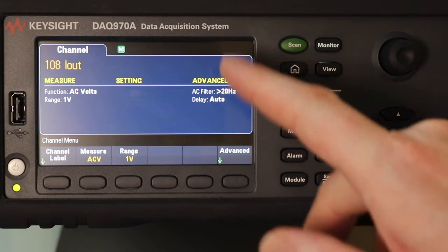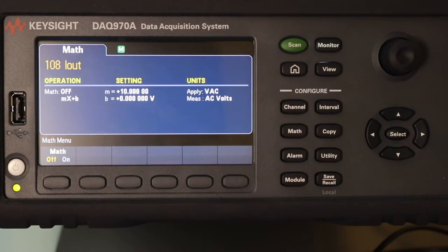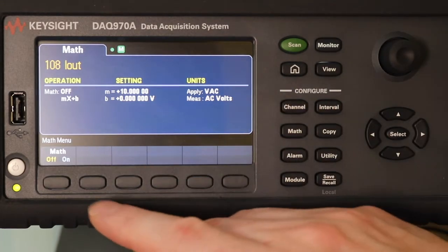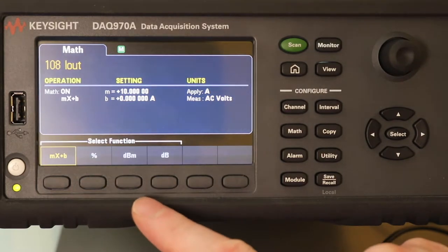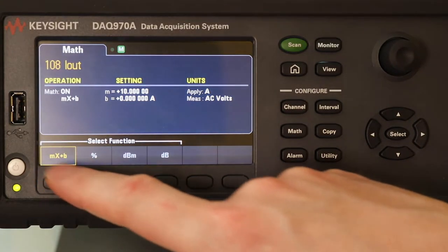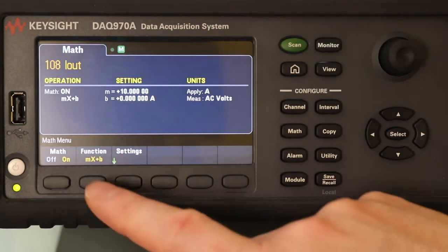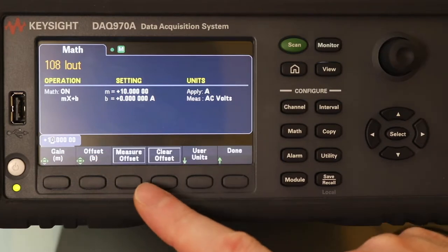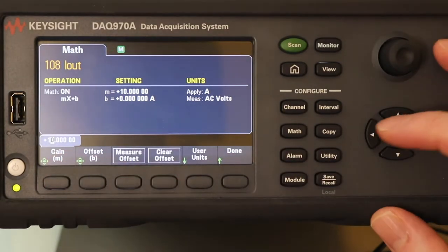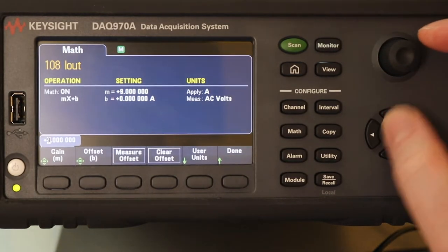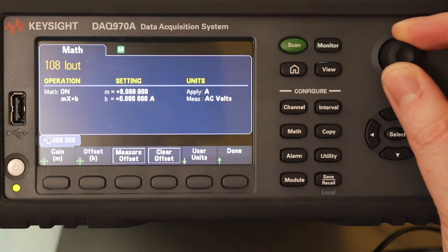To convert this into amps, I'm going to hit the math button. That allows me to apply a formula. If I turn it on, I've got a number of formulas available: simple gain, percentage, DBM. I want MX+B. I'll go to the settings — the gain I want is times 10. I can adjust this with the keys or the knob. So X is 10 times.